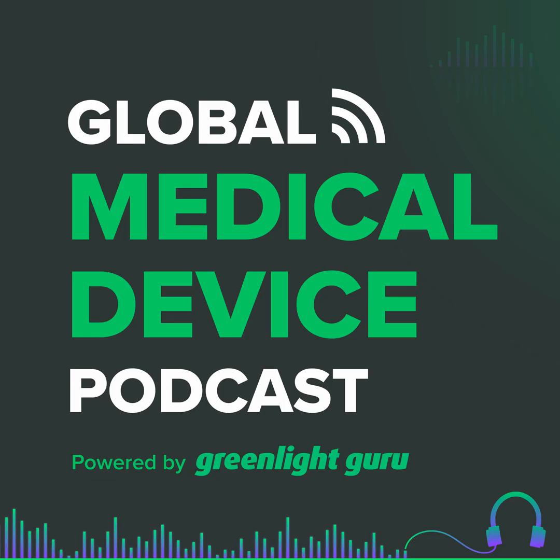Absolutely. When you asked me at the very beginning what the options are, so now we have a third option to the two. I suppose they still fall under the umbrella of disclosing to the FDA. However, my mind thinks very hierarchically, categorically, and so on. So I think in a stepwise function. If I'm a medical device company and it's a small change, a letter to file is probably, well, I shouldn't say the quickest and dirtiest, because it's the same level of burden. You just simply haven't given it to the FDA. It should be anyway. Most companies maybe don't do that, but you have this level, then you have a special 510K. Maybe you have, like I said, the PMA. I almost see this as somewhere in between, but I wonder if you have any thoughts on where you would see it.